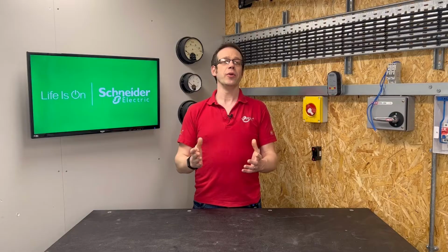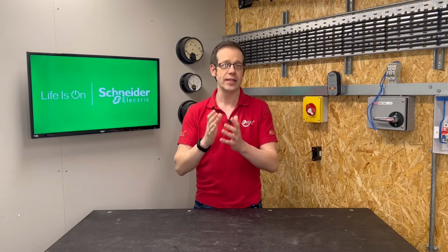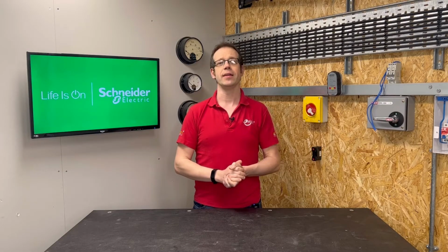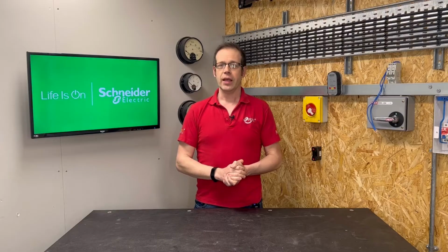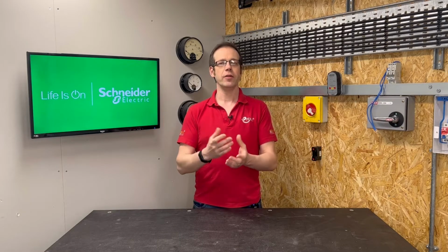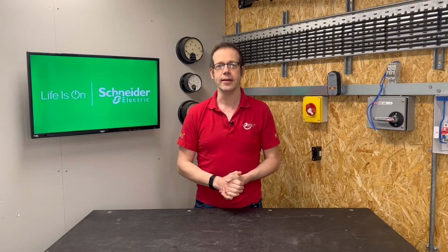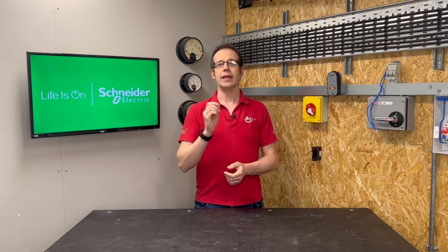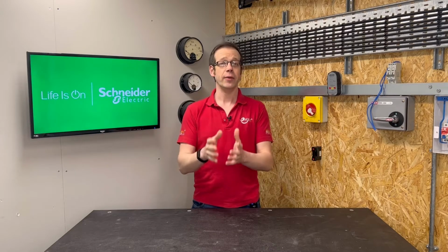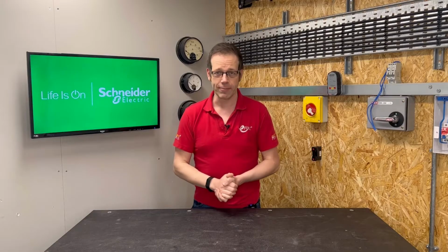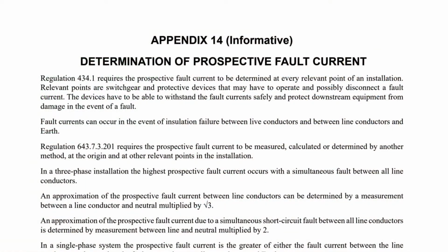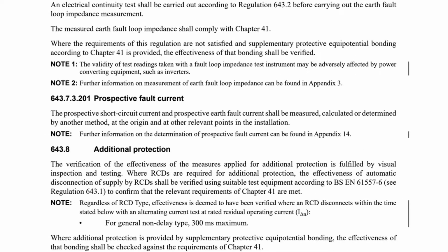And we need to ensure that should such a fault occur, our protective devices are able to withstand the large current that would flow. If we fit a device in a setting where the fault current exceeds the stated ICN, we could be in danger of the device being damaged or, in the worst case scenario, catching fire or exploding. Appendix 14 of BS 7671 gives further guidance on these requirements and the measurements that should be taken. The regulation states the prospective fault current may be measured, calculated or determined by another method.